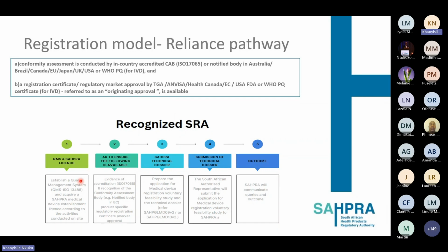When we look at the process for these recognized regulatory authorities, the license holder must establish a quality management system according to ISO 13485, ensure they have their medical device establishment license with activities conducted on site, and most importantly ensure the devices are listed on the establishment license and approved for Class C and D for those specific products. The authorized representative has to ensure they have evidence of accreditation, recognition of a conformity assessment body, and also product-specific regulatory registration or market approval.